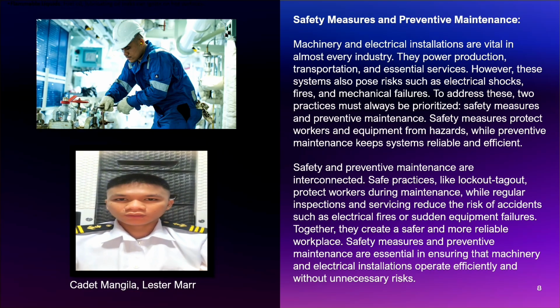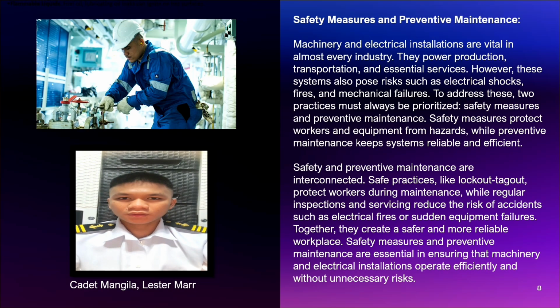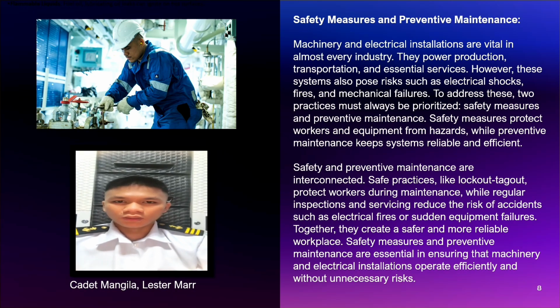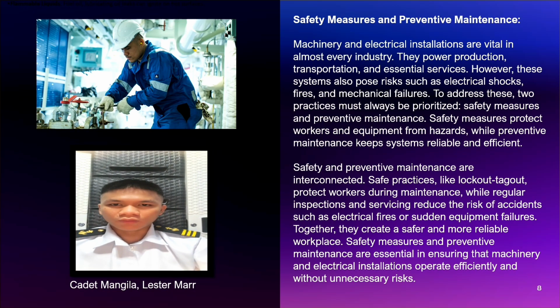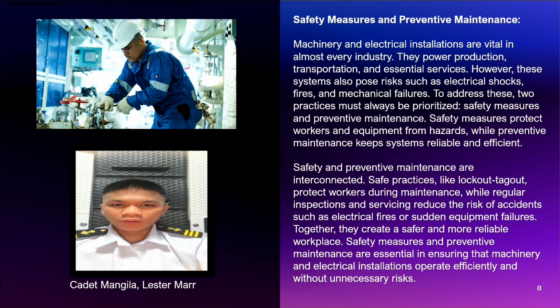Next, lockout tag-out, or LOTO. This is a procedure to make sure equipment is completely disconnected from power before repair or servicing. Ang process ay simple pero life-saving. We lock the switches or circuit breakers and we tag them with warnings para siguradong walang accidental energizing habang may tao na nagtatrabaho. May mga documented cases worldwide where failure of LOTO resulted in workers being electrocuted, kaya critical ito.